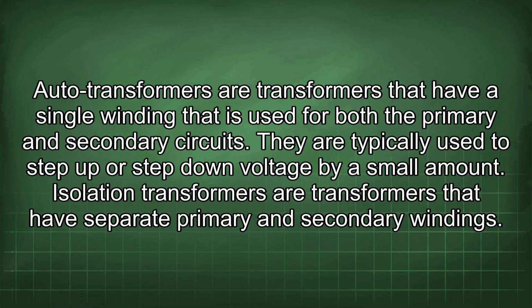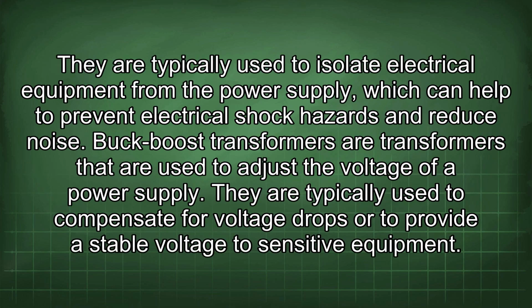Autotransformers are transformers that have a single winding that is used for both the primary and secondary circuits. They are typically used to step up or step down voltage by a small amount. Isolation transformers are transformers that have separate primary and secondary windings. They are typically used to isolate electrical equipment from the power supply, which can help to prevent electrical shock hazards and reduce noise. Buck-boost transformers are transformers that are used to adjust the voltage of a power supply. They are typically used to compensate for voltage drops or to provide a stable voltage to sensitive equipment.